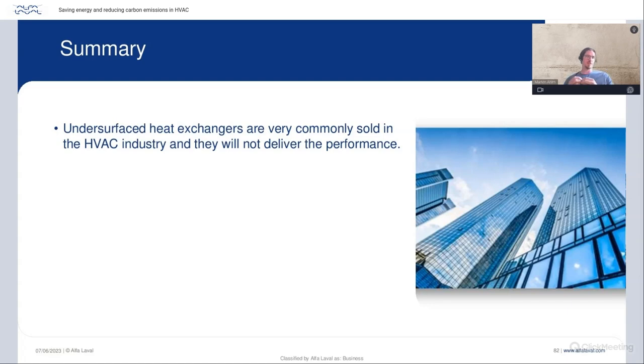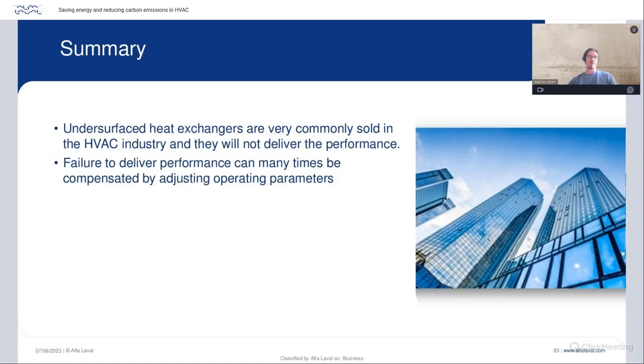So just the conclusions here, very shortly. The summary is that undersurfaced heat exchangers that are not delivering the performance are, unfortunately, in many, many markets the standard solution used in the HVAC market. When a unit doesn't deliver, it can be compensated by adjusting the evaporation temperature, for instance on the chiller, but that will always drive higher energy bills.